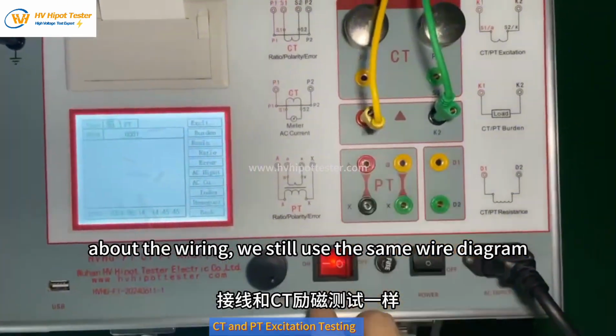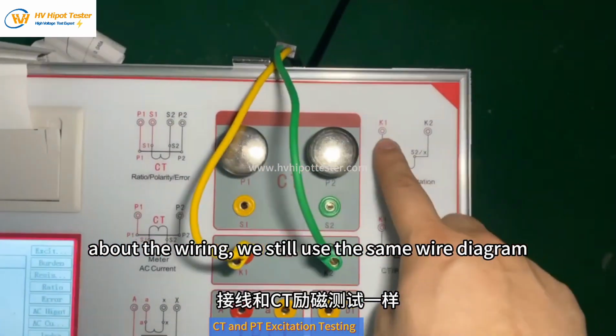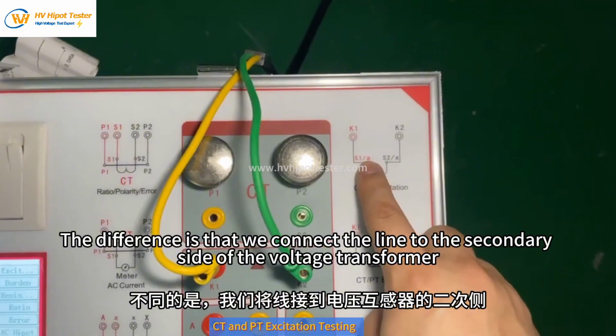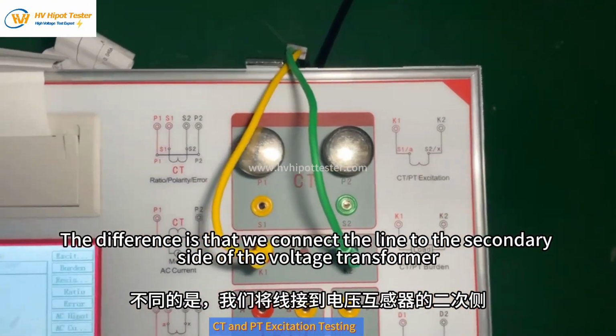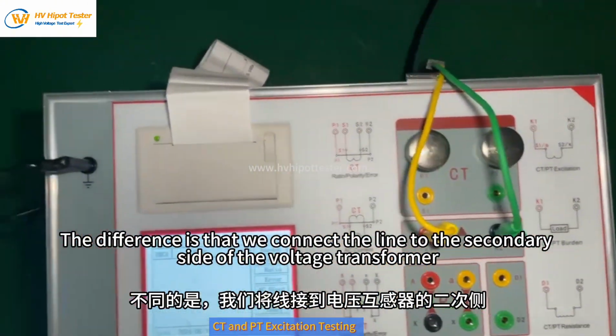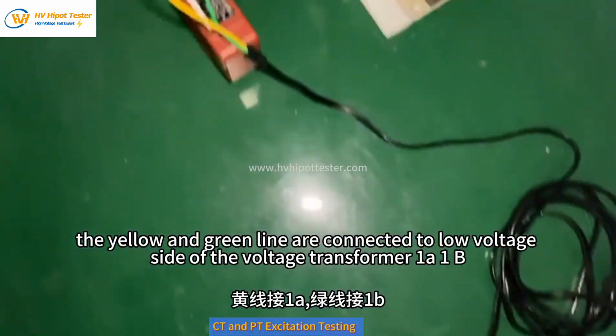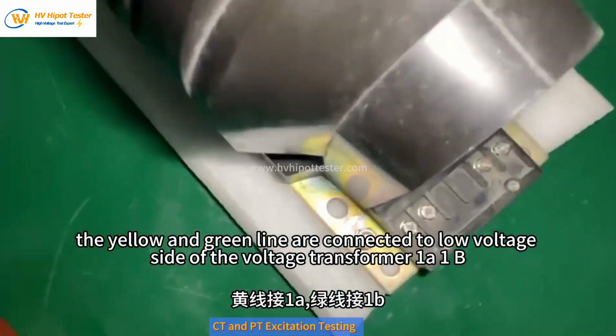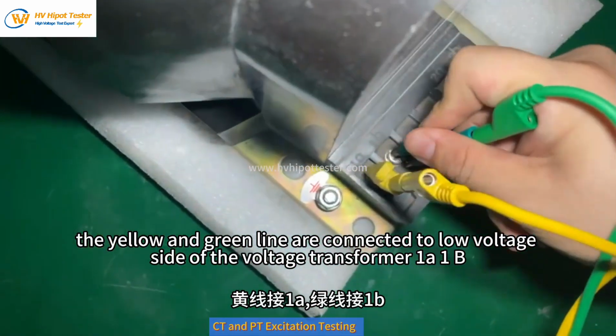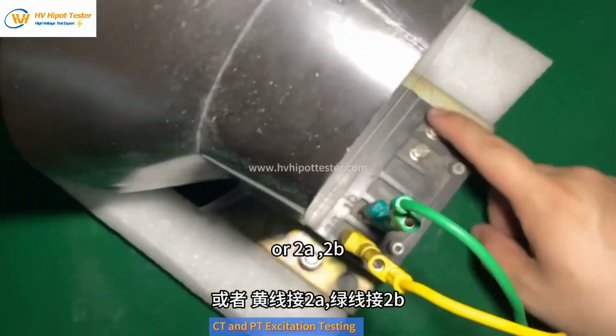Now let us introduce PT excitation testing. About the wiring, we still use the same wiring diagram. The difference is that we connect the line to the secondary side of the voltage transformer. The yellow and green lines are connected to the low voltage side of the voltage transformer, 1A 1B or 2A 2B.